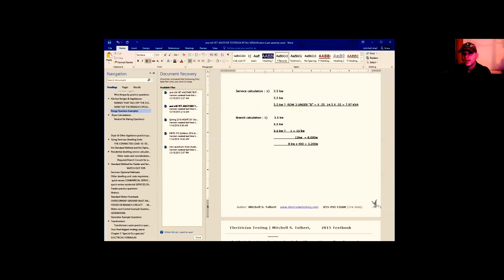So there I'm rounding that up to a 15 kW range, but I'm doing that because I'm on row 1 and I'm past 12 kW when I do that adding. So that 14.5 kW becomes a 15 kW range. And the first 12 kW of that number equals 8,000, so that doesn't change on me. That's still the same math there, right?